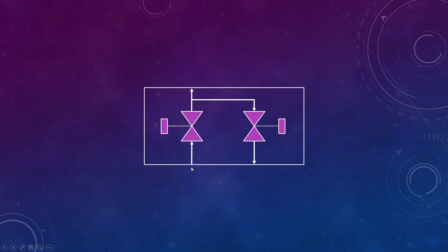There is connection 1, connection 2, and connection 3. Connection 1 is the process connection, which will be connected to the process so that the process medium will enter into this valve. Connection 2 is the instrument connection, where the field instrument — for example a pressure transmitter, pressure switch, or pressure gauge — will be connected.